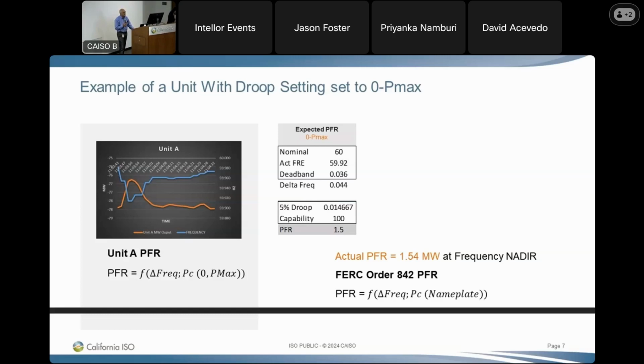And in this case, again, every example, I have a couple of examples I'm going to go through. These are battery storage units that I've used in this example. If you look at the droop calculation, which is on the right, how much response you provide is directly a function of how low the frequency went and what your droop setting was. In this event the frequency went down to 59.92 hertz, and the unit was a 100 megawatt unit. So you plug that into the capability.